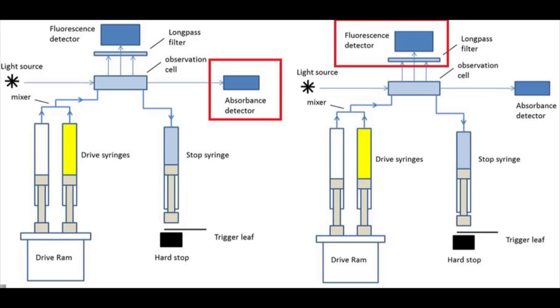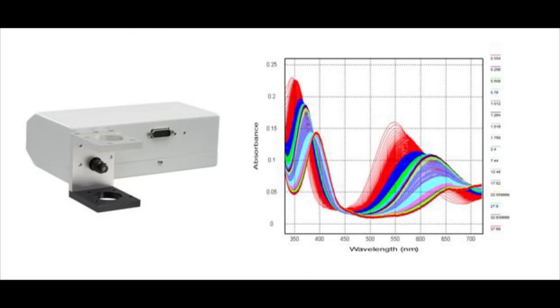To do this we most commonly use a xenon arc lamp light source. We pass this light through a monochromator that allows us to select the particular wavelengths of light that we are interested in. Alternatively, for absorbance measurements we have the option to measure all wavelengths simultaneously using a photodiode array detector.